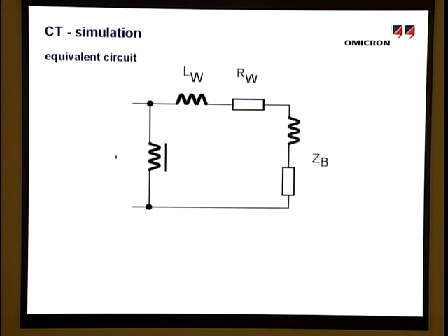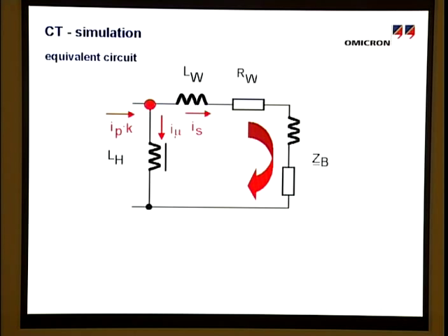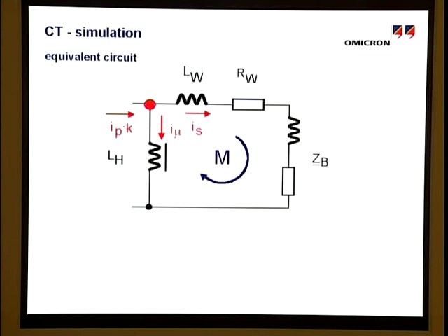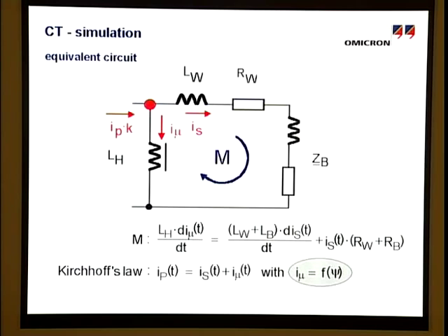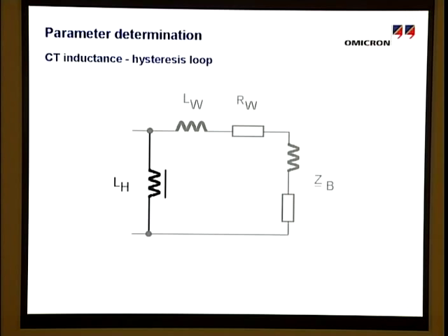According to Kirchhoff's law, at the red node, the secondary current is merely the image of the primary current, distorted by the magnetizing current. The secondary current is of special interest because it flows through the relay, and it can be calculated via the mesh M and Kirchhoff's law. Special attention has to be paid to the magnetizing inductance, which is a non-linear element due to the magnetic behavior of the iron core, known as the hysteresis loop.